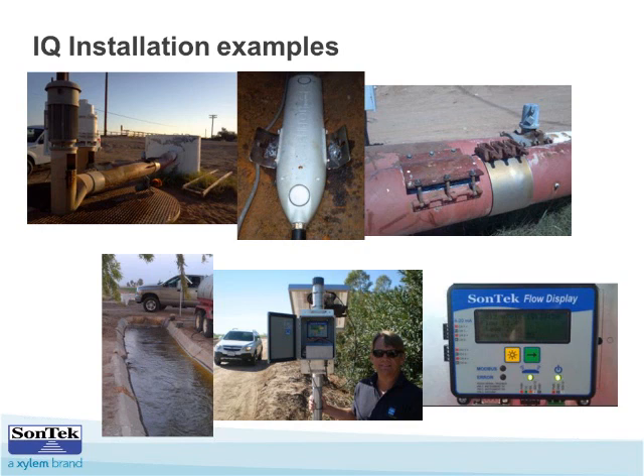One question: how do you secure the IQ on a gravel, sand, or cobble bed? There are probably many creative ways to do that. We've seen it done near Bishop, on cobble in a natural river, using about a 2-foot by 2-foot concrete mount so it's negatively buoyant and keeps the unit down in the bed, then you attach your conduit to that and bring the cable out.